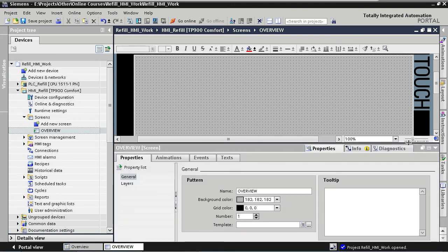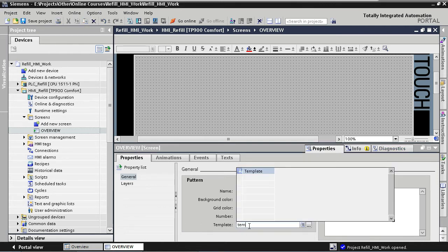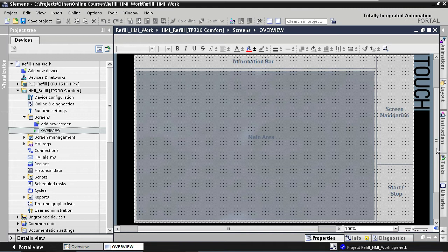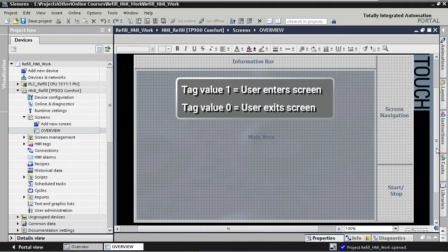Under general properties we can choose to assign a template to the screen. We enter the name of our template, 'Template,' and you can see our screen has received a template layout. So every time this screen is active in runtime, all the features of our template will be available to the user. The next thing we need to do is assign a zero or one value to our local boolean tag depending on whether the screen has been loaded or cleared — value one when the user enters the screen, and value zero when the user exits.